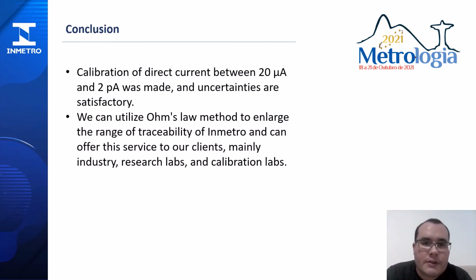These values and uncertainties will enable the validation of the capacitor charging method that is being implemented in the laboratory. With the system implementation, Inmetro expands its measurement and calibration capabilities in direct current by 6 orders of magnitude. We, therefore, concluded that it is possible to calibrate direct current below 20 microamperes to the order of picoamperes with satisfactory uncertainty, and soon we will be able to offer this service to our customers, such as industries, calibration laboratories, and research laboratories.